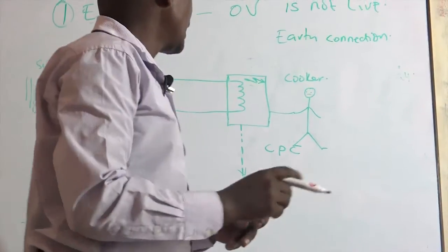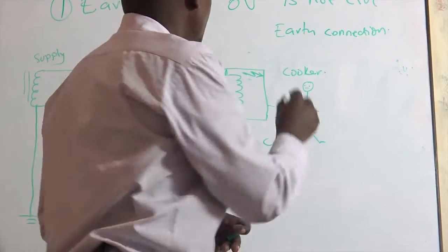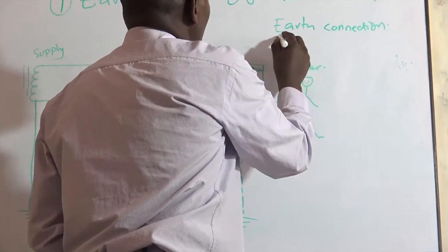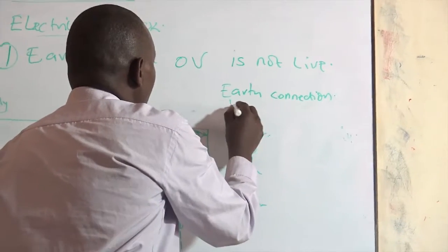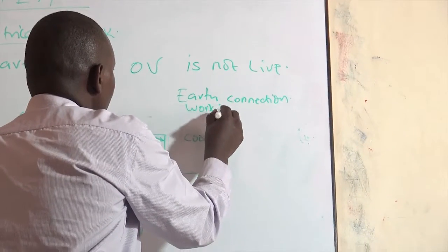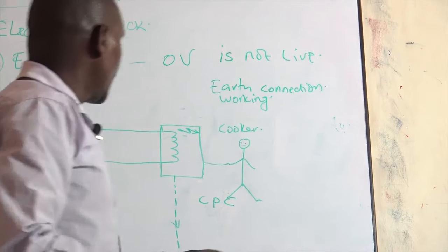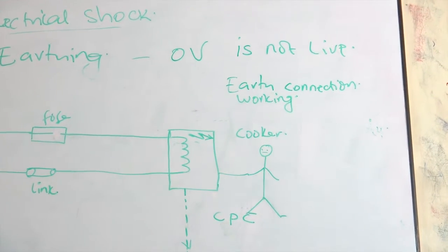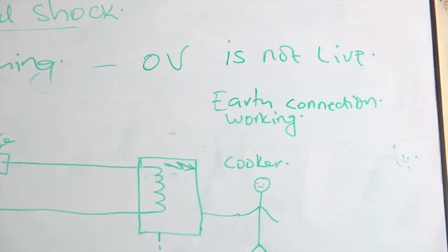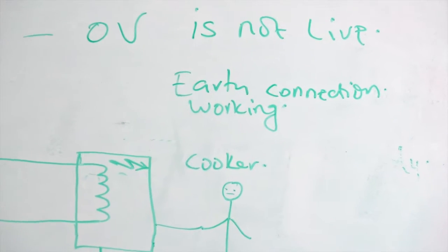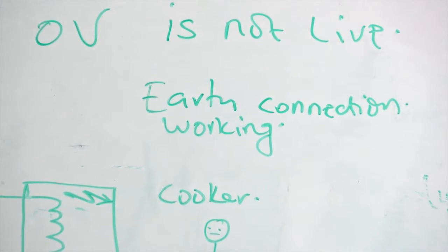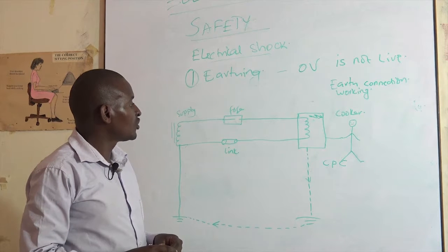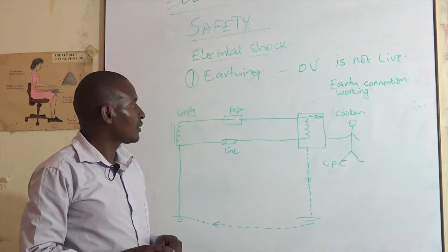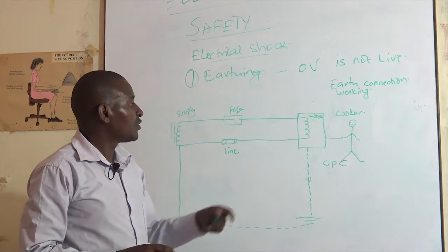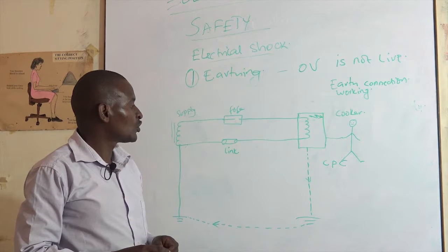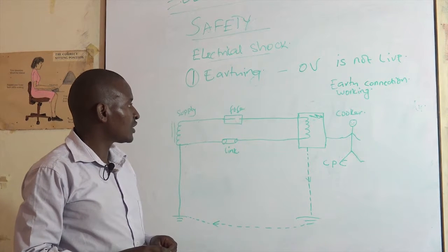They should have an earth connection that is working. And you should get a qualified technician to check whether your installation has a proper earthing system, so that in case of such a fault, the person who is using the cooker or any other equipment remains very safe and is not exposed to unnecessary risks of an electric shock.